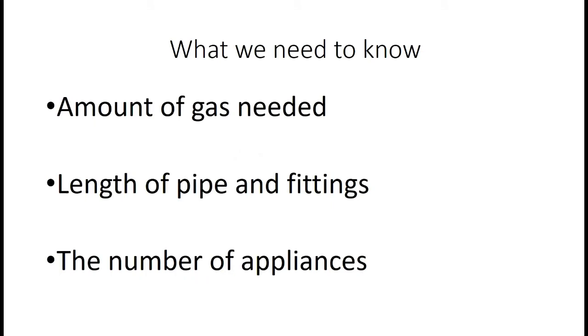The first thing you've got to work out is what you need to know, and you only need to know three things: the amount of gas that you need to be delivered through the pipe, the length of the pipe and the amount of fittings there are, and very importantly, when you're talking about multiple appliances, the number of appliances on the system.